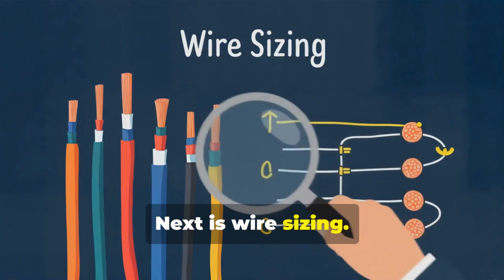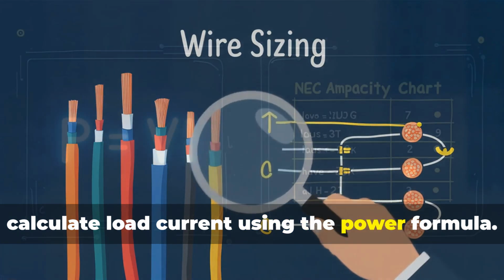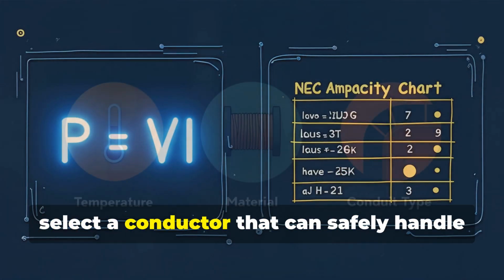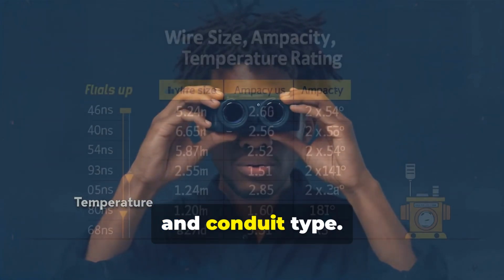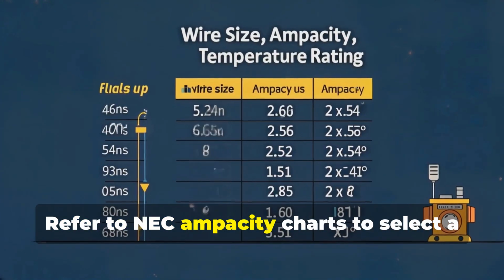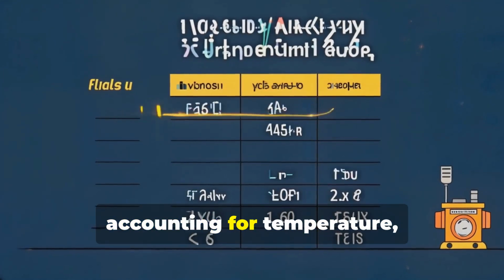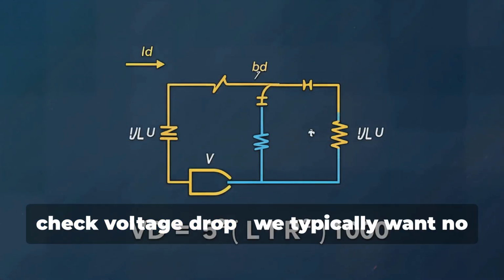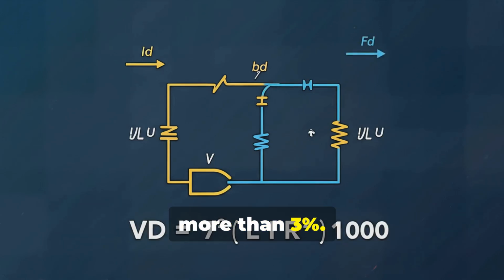Next is wire sizing. First, calculate load current using the power formula. Then refer to NEC ampacity charts to select a conductor that can safely handle that current, accounting for temperature, material, and conduit type. Finally, check voltage drop. We typically want no more than 3%.